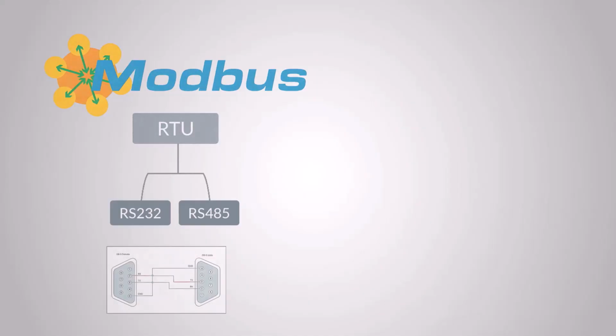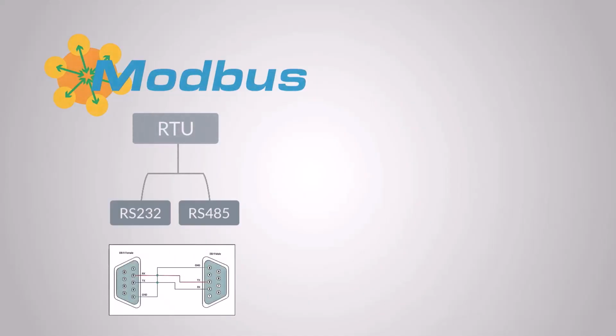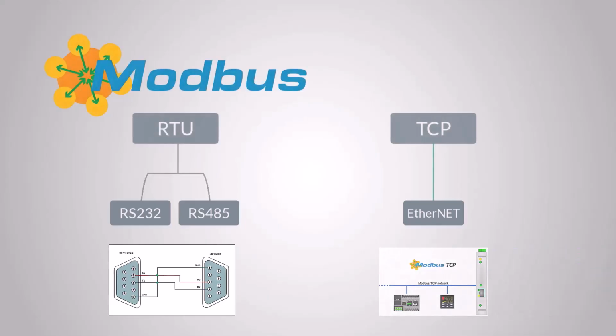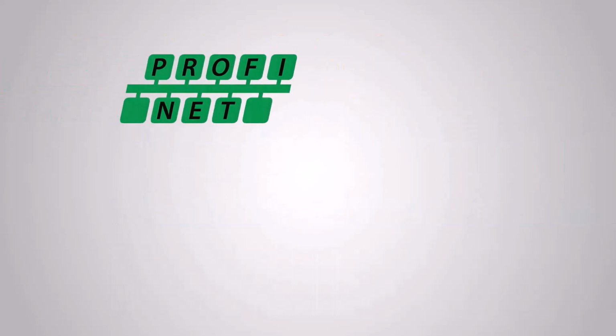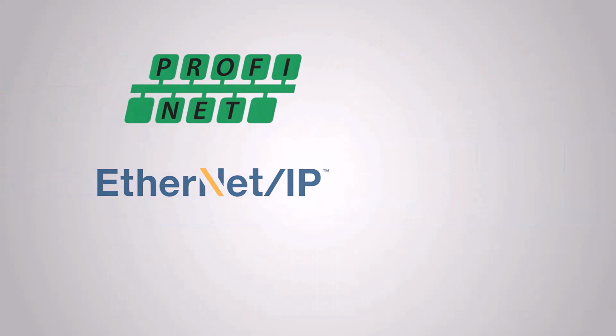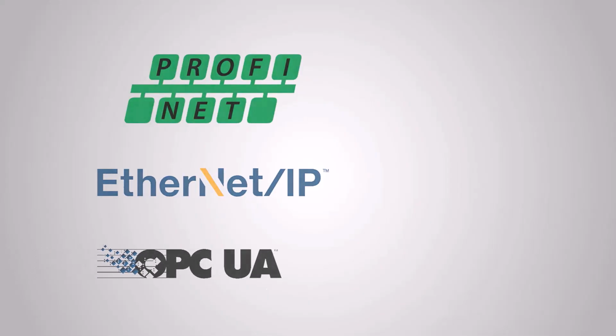It's compact and widely supported, making it ideal for simple or legacy setups. Modbus TCP runs over Ethernet, offering higher speed, better scalability, and easy integration with IT networks. Other advanced options include Profinet, Ethernet/IP, or OPC UA for deterministic performance and enhanced security.